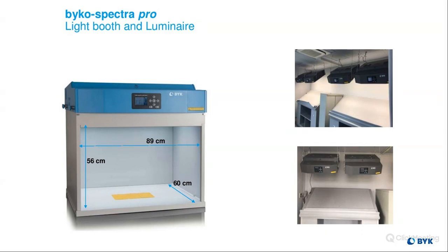And lastly, we have our byko-spectra pro, which is our premium model here. You see the dimensions internally for it. And this is special because you not only can use it as a light booth, but you can also use it as a luminaire. So earlier I spoke of some examples of if you had a car bumper that couldn't normally fit inside of the booth, you can set it up as a luminaire where you just attach it to the ceiling and it shines down over an angled desk, and you can set the samples on there and then view it from 0 degrees from the side. So that's the different setup options for it.